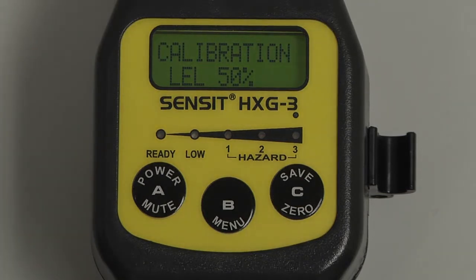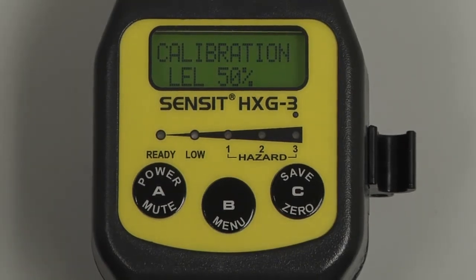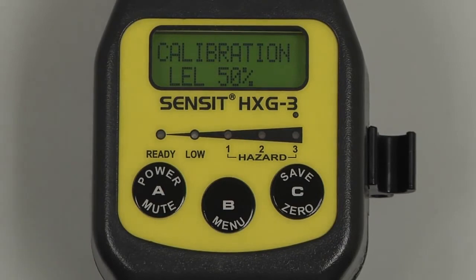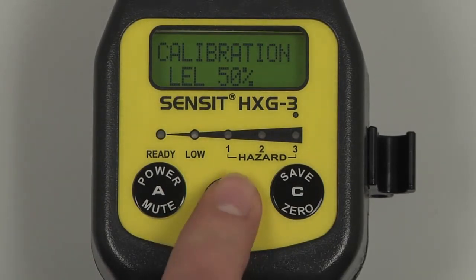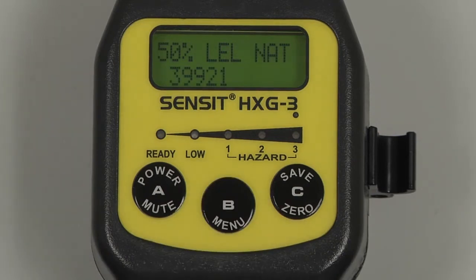So we can attach the regulator to the calibration gas, turn on the regulator, and attach the cal adapter to the inlet at the end of the gooseneck. Select by pressing and releasing the B button, and the calibration process will begin. On the display, we have a number for the raw output of the sensor. This number is useful as a reference when troubleshooting if any issues should occur.